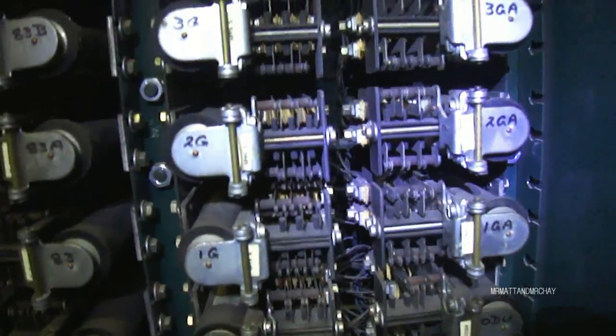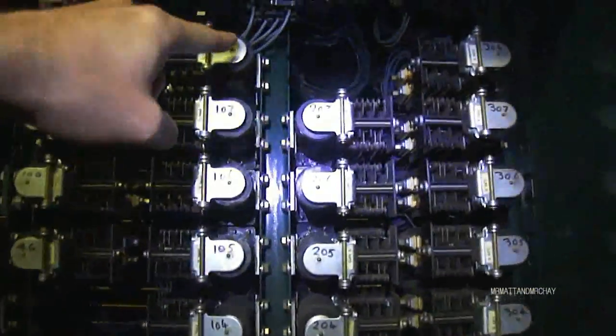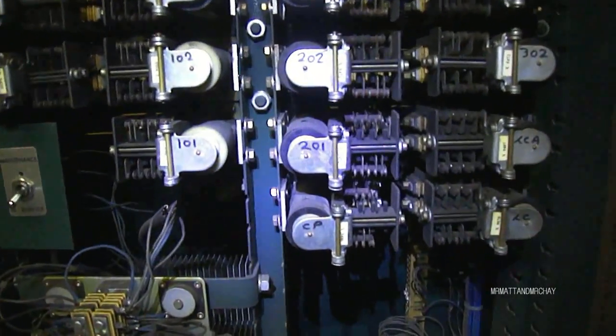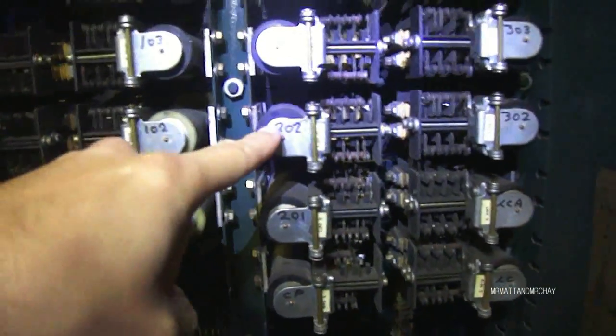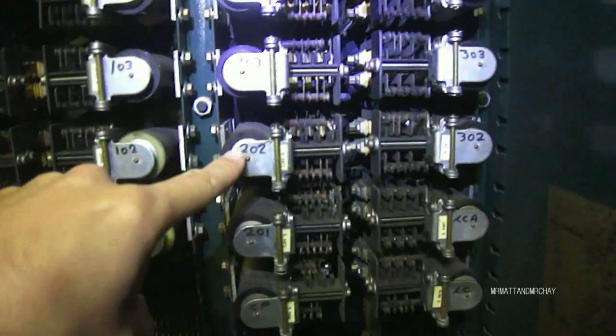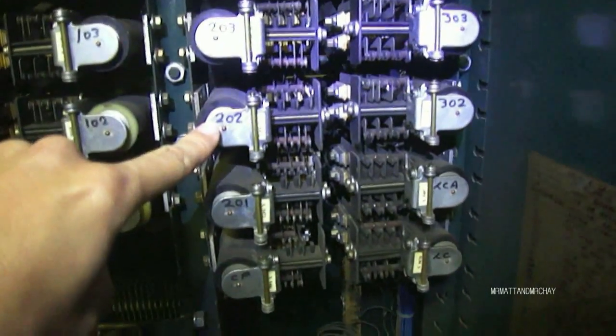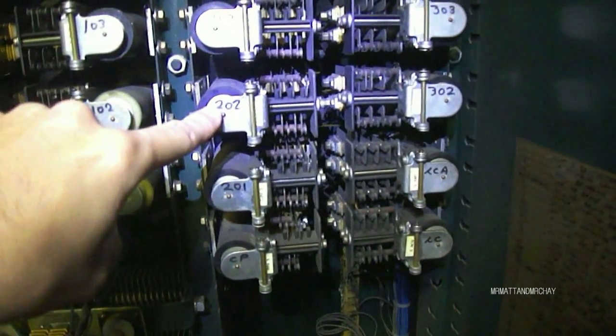These relays are on, and what we're going to do now is follow these relays up to the top. So if I give it a car call on the top floor, it should go up. In fact, to give me a little bit of time to get the right camera angle, I'm just going to give it an up button on the floor where the car is currently positioned, just to open the doors and give me a bit more time. There we go. Give it a top floor button. That's done. Now we're going to follow these relays. It's on the first floor at the moment.